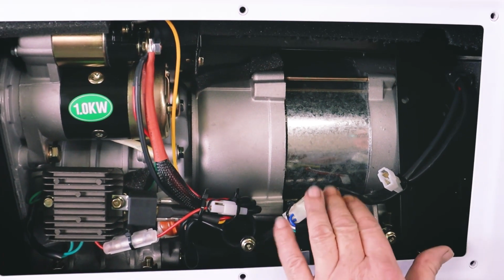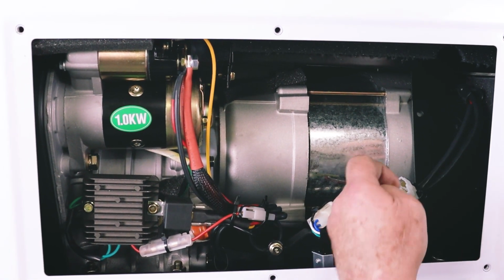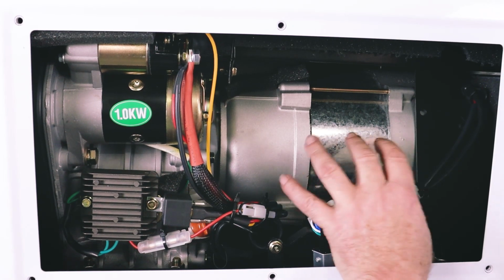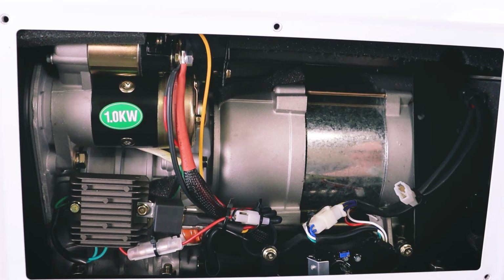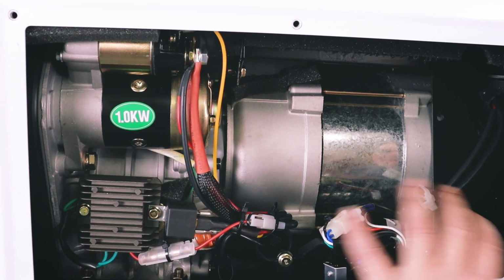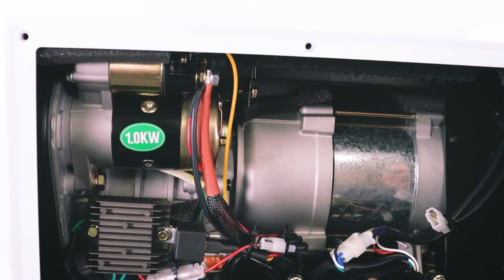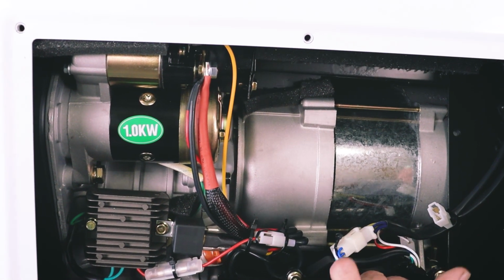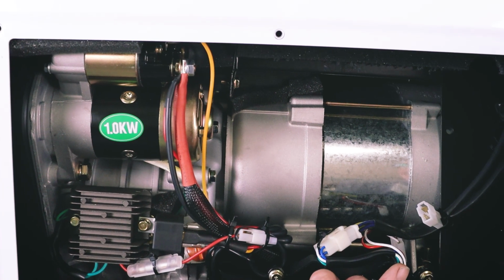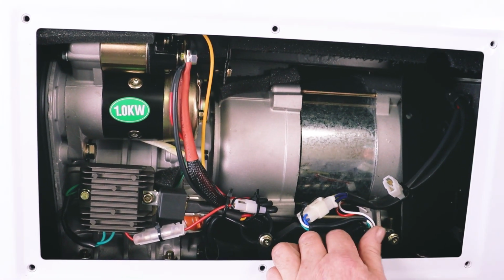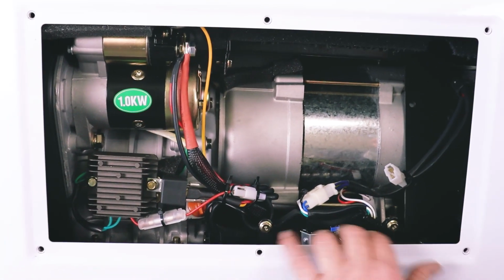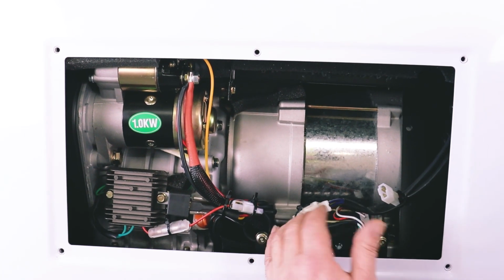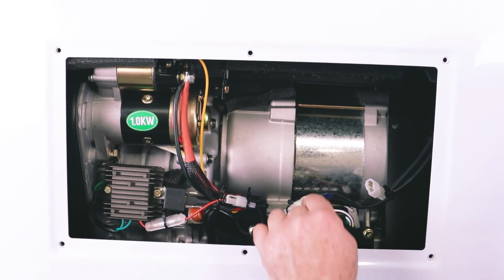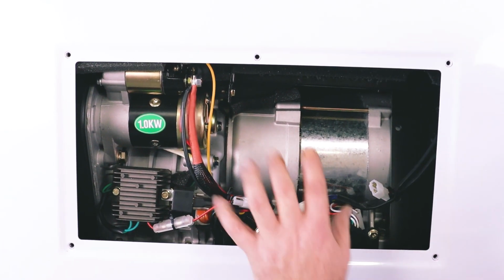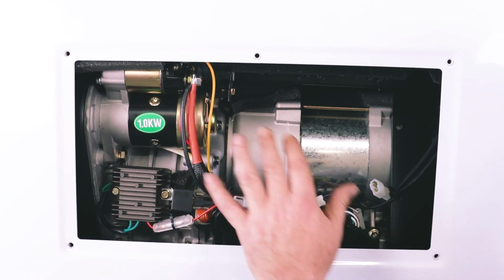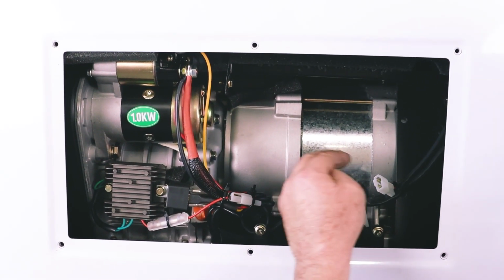The AVR puts a DC voltage onto the brushes, which powers up the rotor of the generator. The AVR varies the voltage depending on what it's seeing coming out, so typically an AVR could be anywhere from the 16 to 20 volt range. Let's say 18 volts, and it adjusts itself up and down minimally to keep the output voltage consistent.